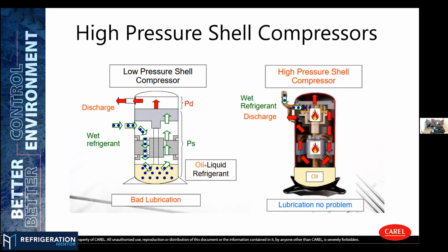On the other hand, a twin rotary compressor with BLDC technology has a different approach. We have our suction line going directly into the mechanical part of the compressor chamber, where the compression occurs. All this mass of the compressor is at the discharge temperature of the compressor. That's why we call it a high pressure shell or a hot temperature shell, because the compressor is very hot. If a few droplets come back from the evaporator, they will instantly evaporate, because there is a huge mass of compressor at a higher temperature and a few droplets at low temperature. This mix makes the refrigerant evaporate automatically.